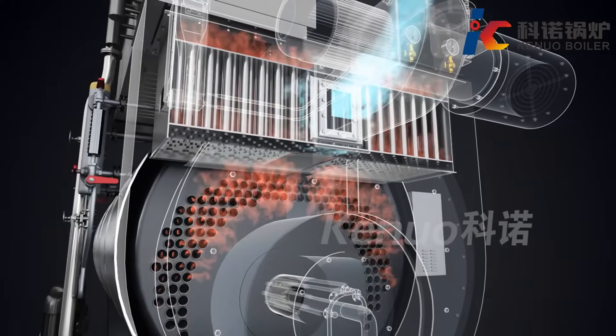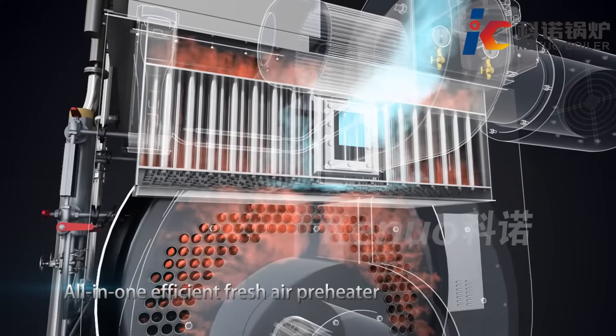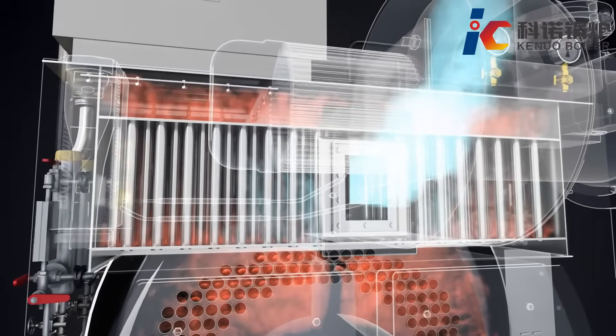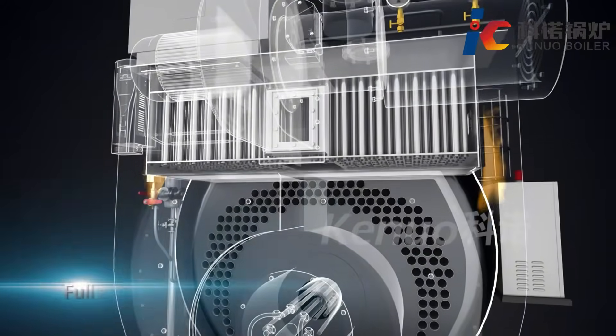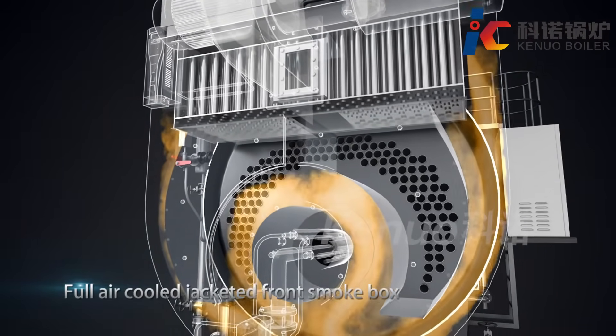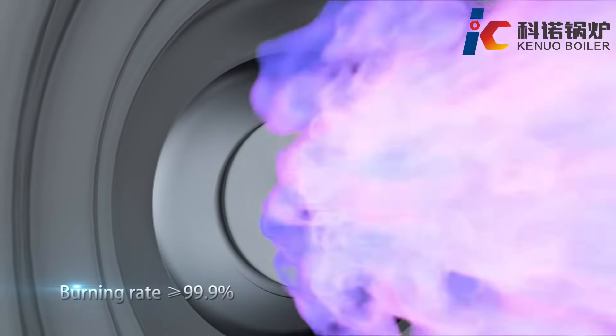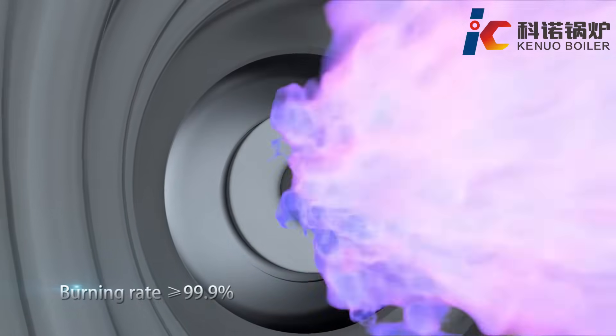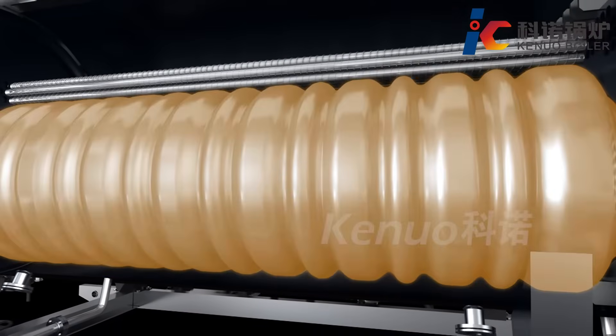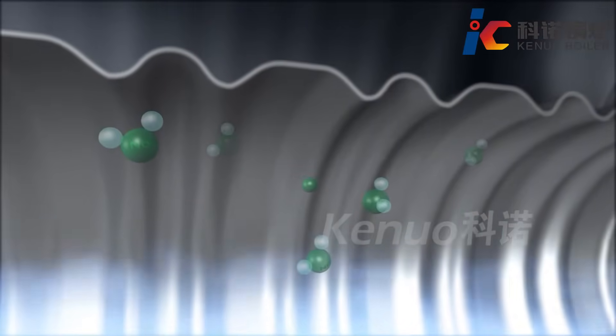The front chamber adopts an air-cooled jacket design and is integrated with an air pre-heater. Part of the flue gas is mixed with the combustion air in the air pre-heater and enters the furnace from the air duct inside the front chamber. This increases the combustion air temperature and burner efficiency up to 99.9%. Recirculated flue gas lowers the combustion temperature, further inhibiting the generation of nitrogen oxides.